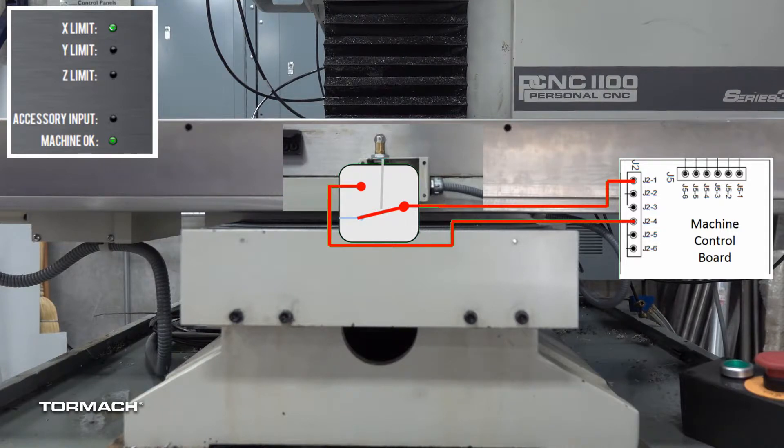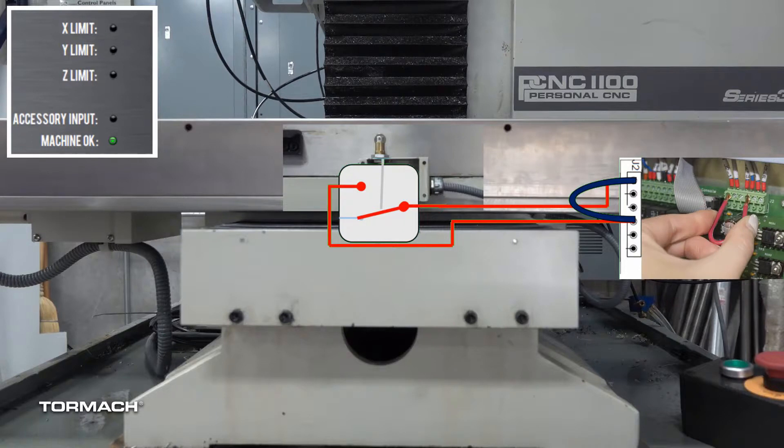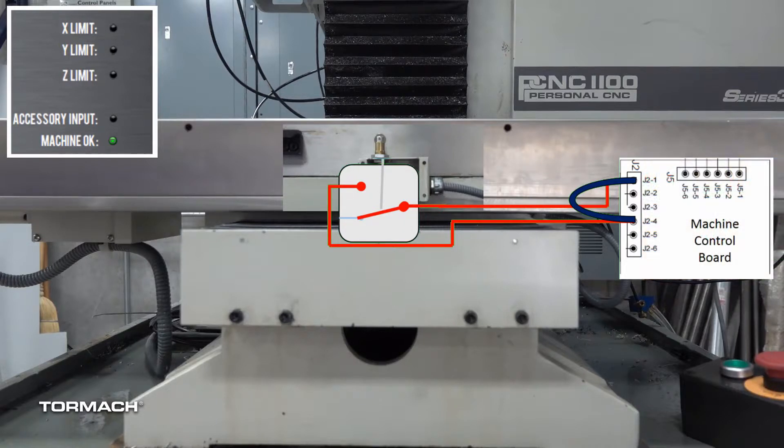Our diagnostic steps guide you to test the limit switch circuitry with a small jumper wire, first at the machine control board, and then at the limit switch enclosure.